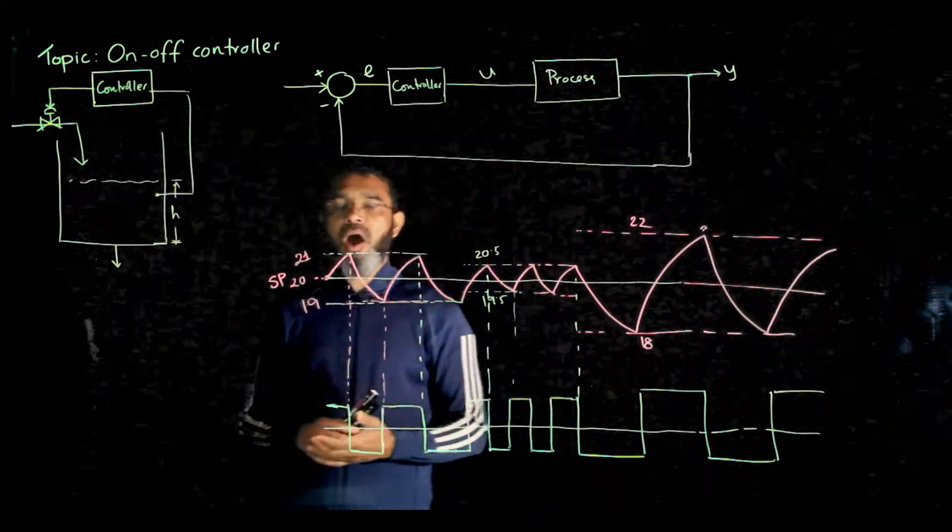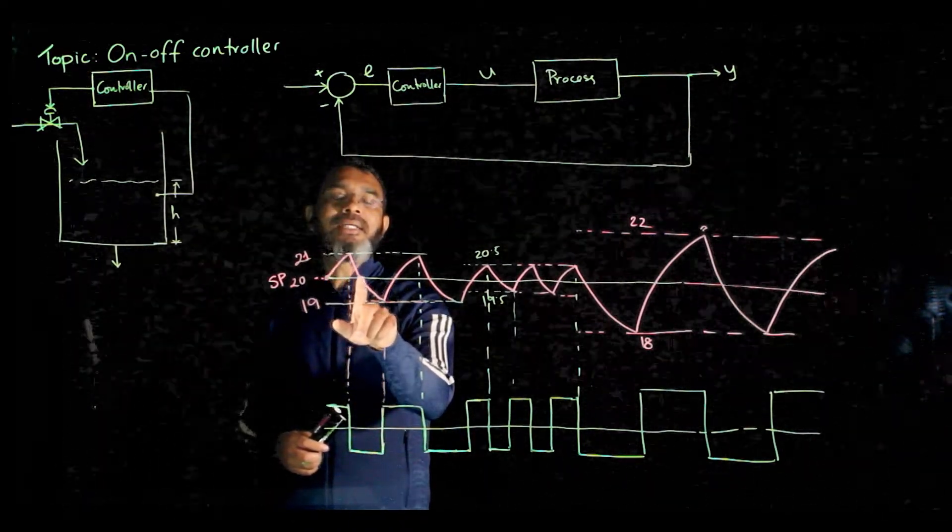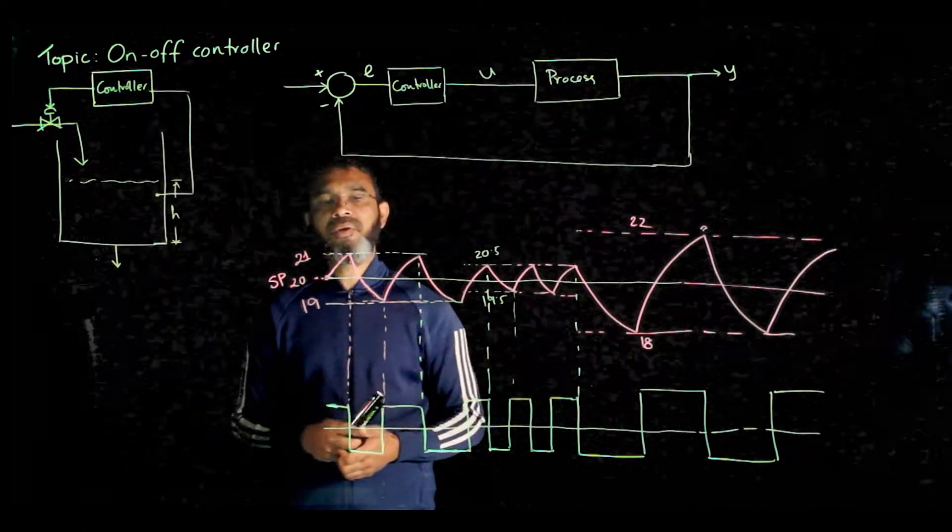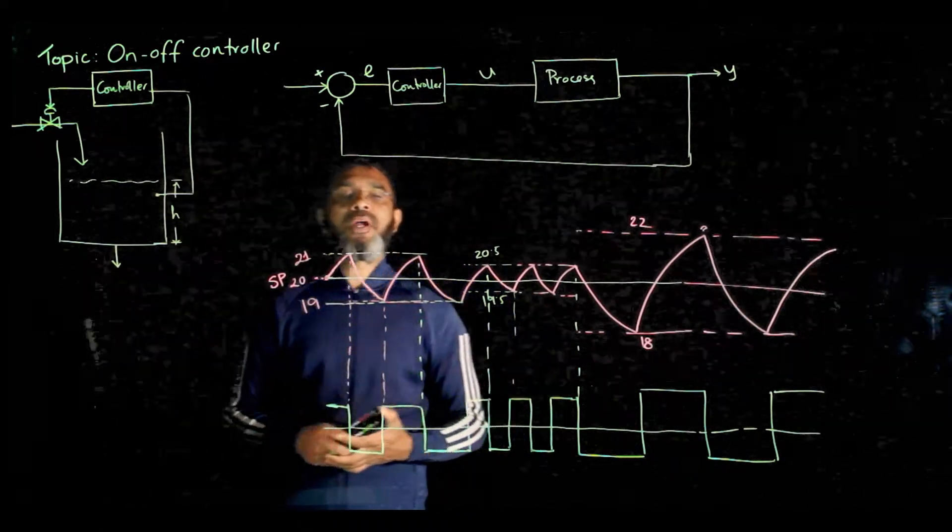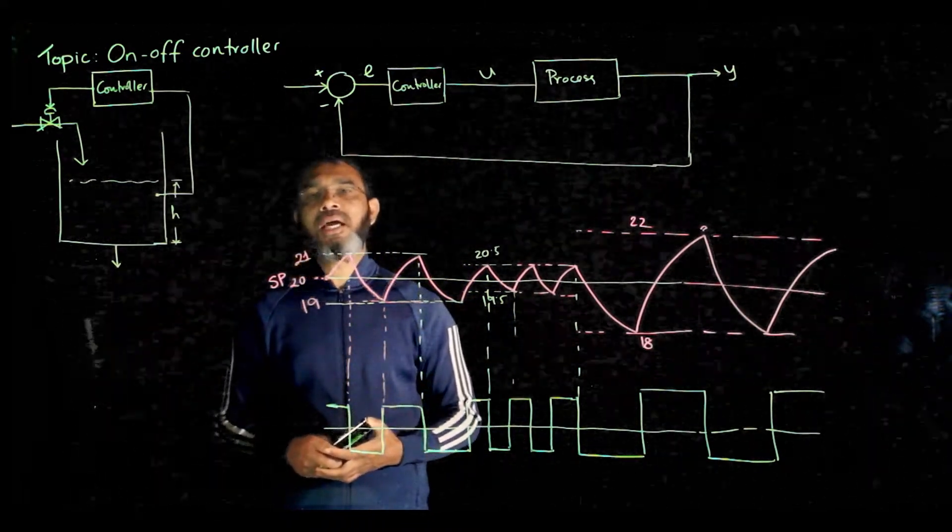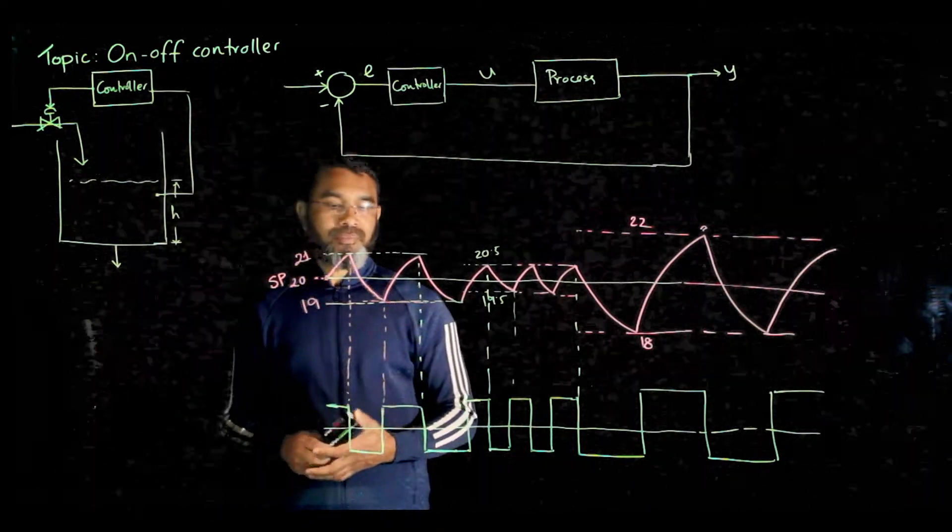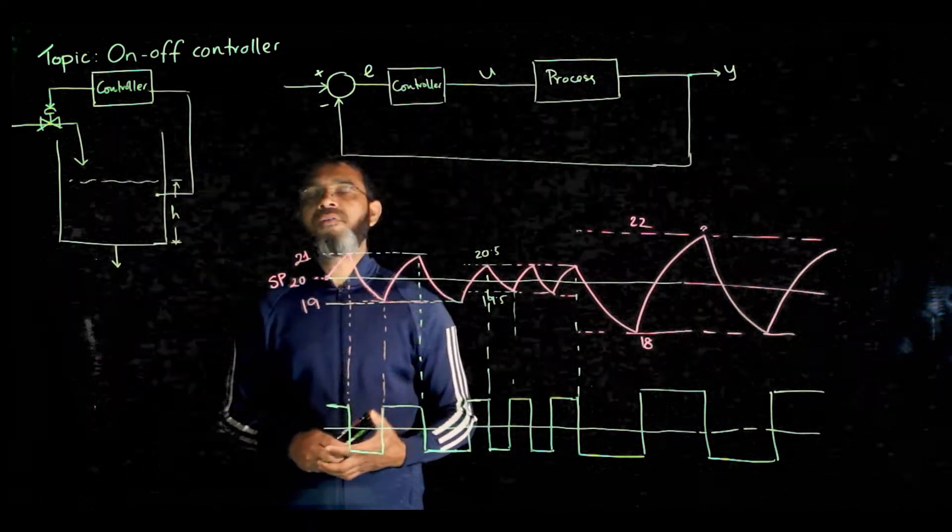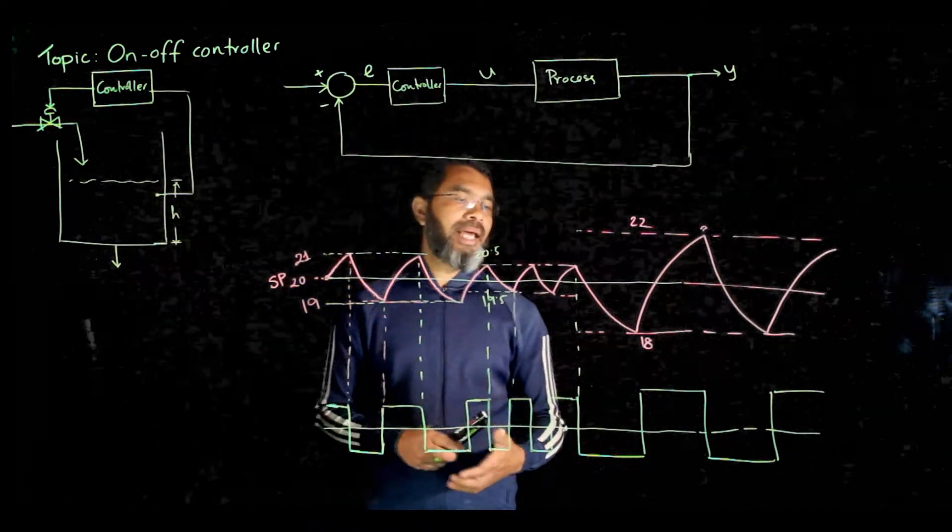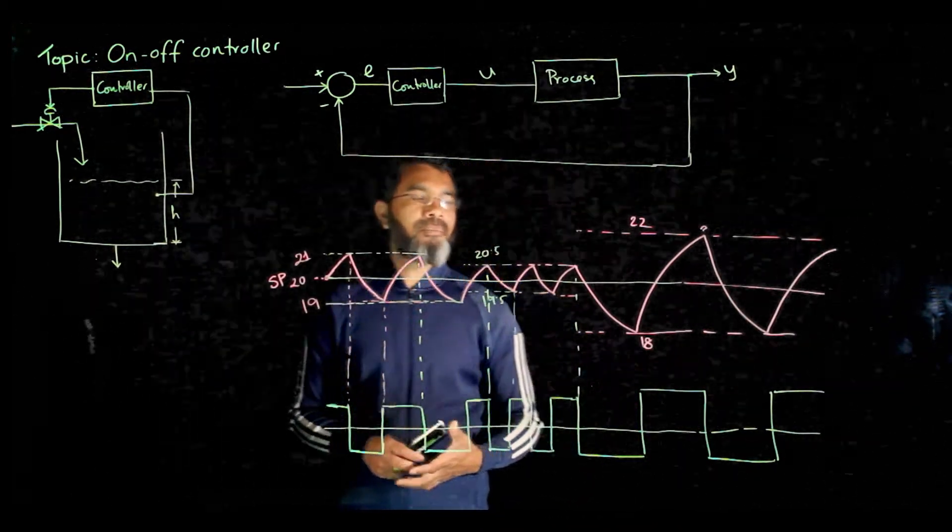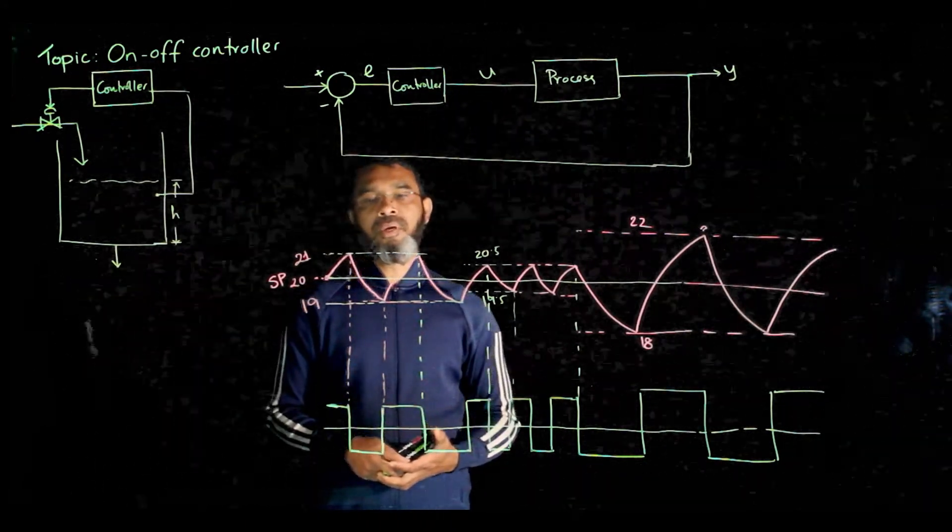So you see that for the on-off controller, one thing is that the output is never steady at the set point value. Rather, it oscillates around the set point between the upper limit and the lower limit, which is called the bandwidth. If you want the bandwidth to be narrower, the turning on and off of the controller will be more frequent. If you can tolerate a wider band, in that case the turning on and off will be less frequent, but that variable will be away from the desired value. So this is the problem with the on-off controller.